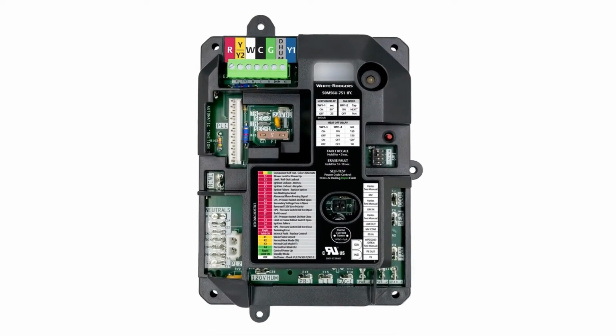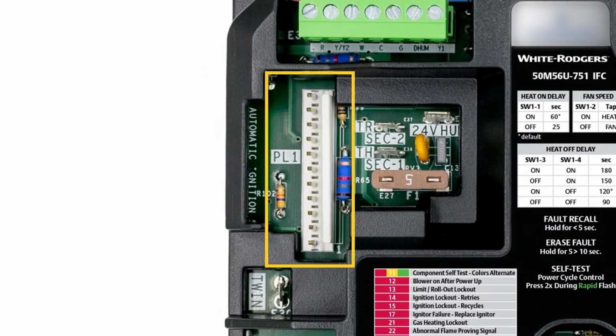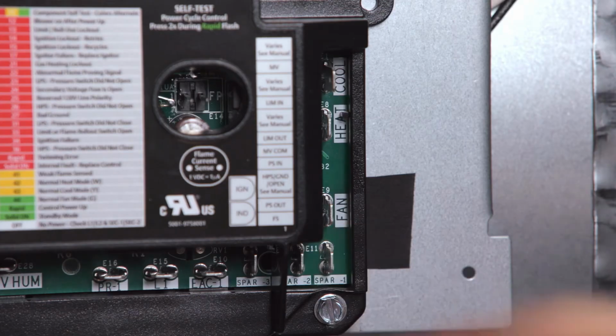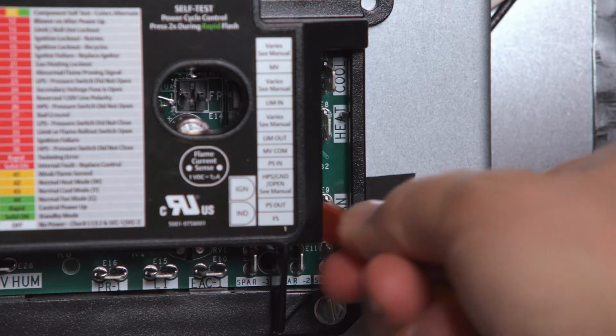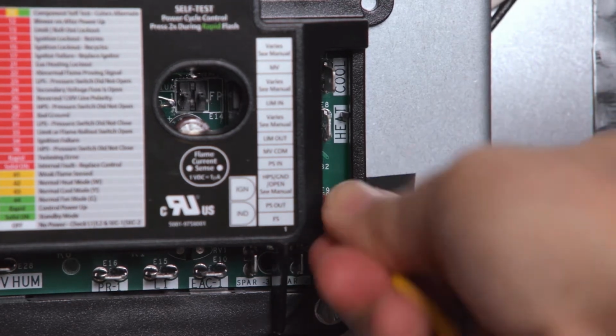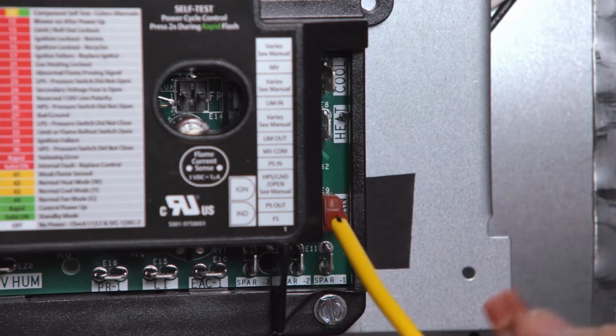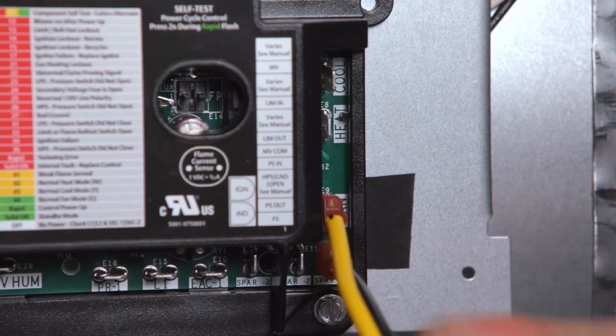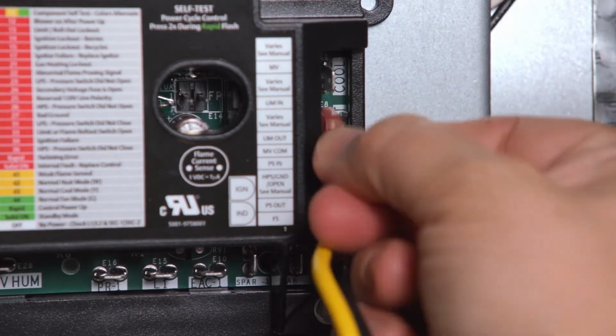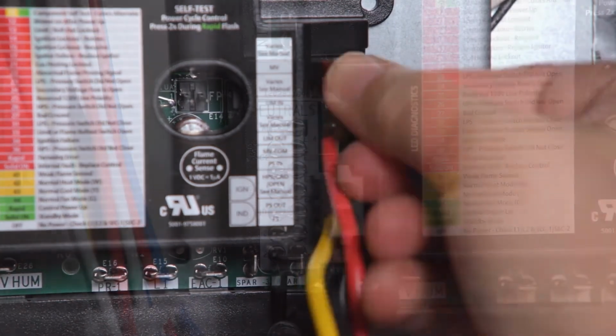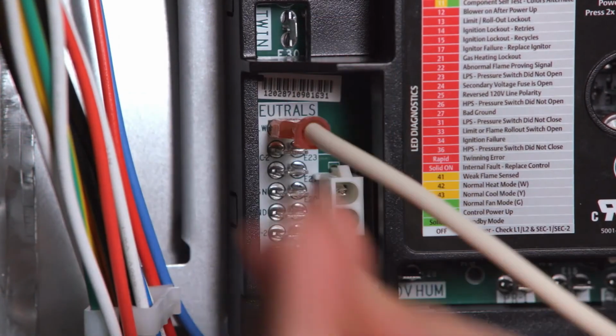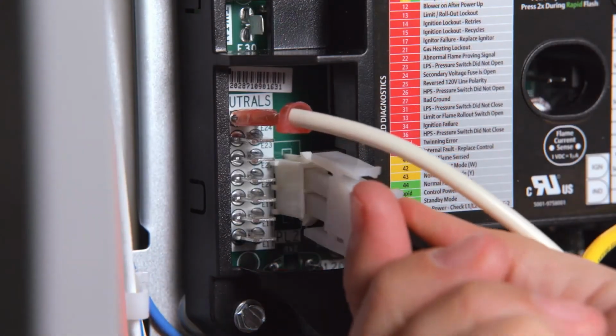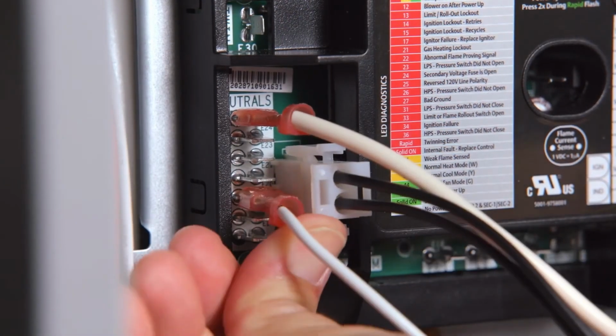In most Carrier units, such as this one, the factory wiring connects directly to the control, so no adapter harnesses are required. The new board allows for a separate fan-only speed. Choose one of the spares to attach the fan-only terminal if desired. Install the blower motor wires for spare, heat, cool, and neutral. Plug in the 2-pin Molex plug and neutral wires.